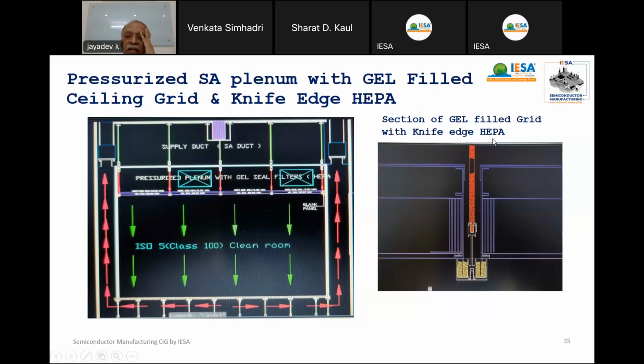So for this, we use gel-filled grid with knife edge. You can see this is the grid. This grid is fixed to the ceiling, and you can see here gel is filled in this. And then these are filters. These are also filters. The knife edge is inserted into this, so it's sealed properly, so that there is no air flow into the room. Even though it's pressurized, the air will come through only the HEPA filters. So this is another thing.